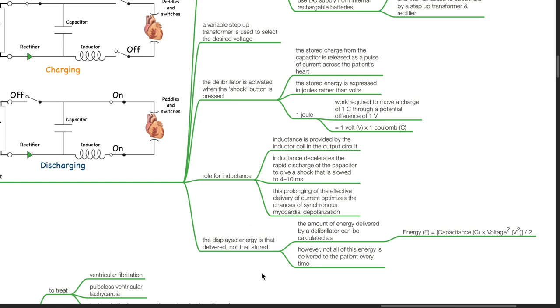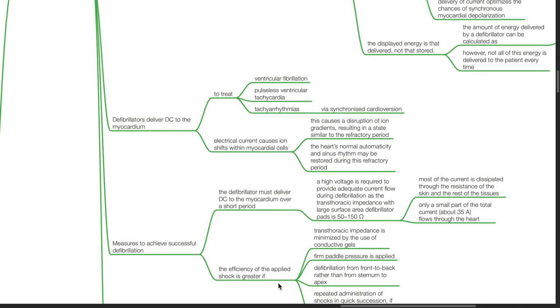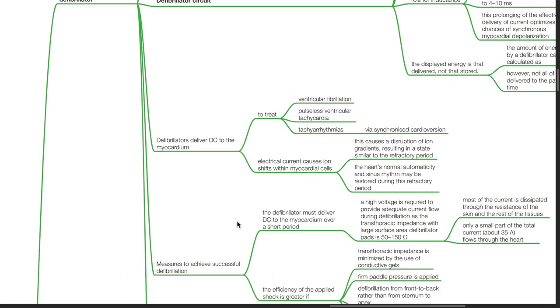However, not all of this energy is delivered to the patient every time. Defibrillators deliver DC to the myocardium to treat ventricular fibrillation, pulseless ventricular tachycardia, and tachyarrhythmias. Electrical current causes ion shifts within myocardial cells, disrupting ion gradients and resulting in a state similar to the refractory period. The heart's normal automaticity and sinus rhythm may be restored during this refractory period.